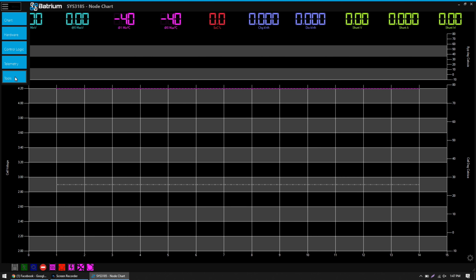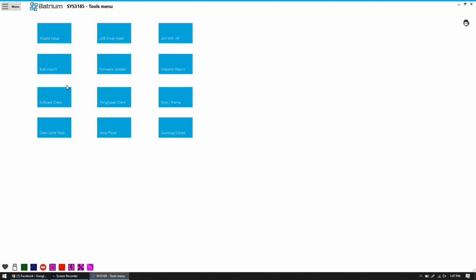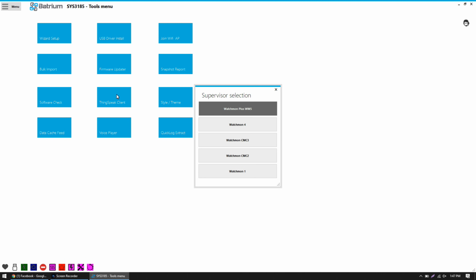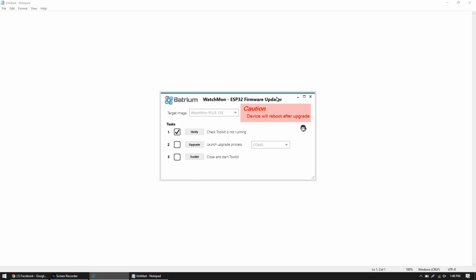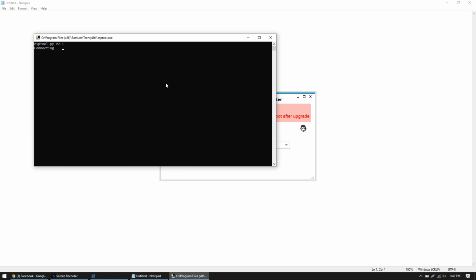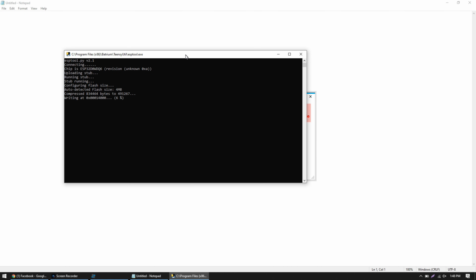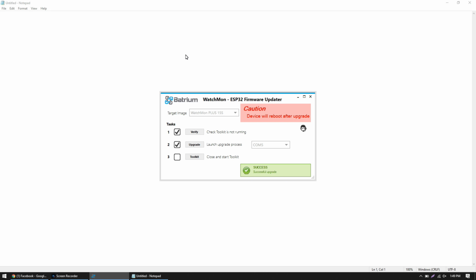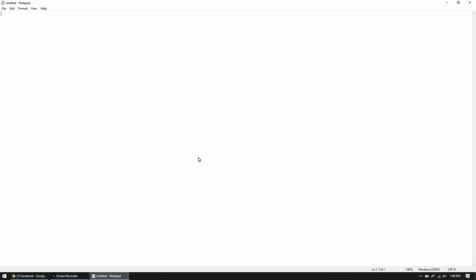Click under Menu, go to Tools, then Firmware Updater, and we have the Watchmon Plus and Watchmon 5. That will close the software and open up this screen. Verify the software is not running, make sure you have the correct COM port selected, and click Upgrade. It uploads the firmware, which takes a minute or two, then says successful upgrade, and you can click the toolkit button to reopen the application.